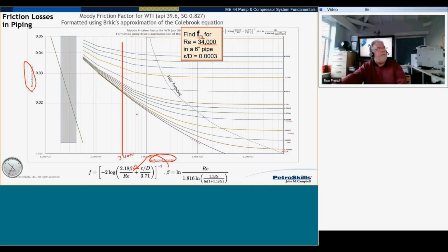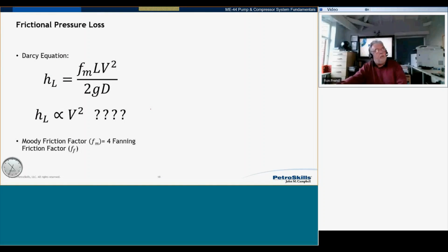It's a 6-inch pipe. The relative roughness is 0.0003, which is right in there somewhere. So we follow this along here, and where it comes up is right there. That's our intersection, and we just read off right across here, and that's our Moody friction factor. In this case, 0.023. Okay, let's do this the hard way now. Let's use our Excel spreadsheet, and we're going to do a calculation. But it's something first I want to warn you about.